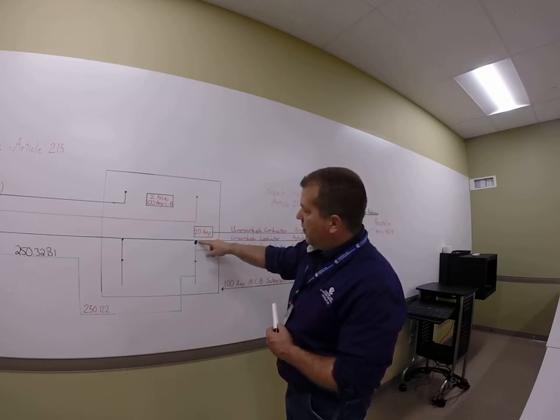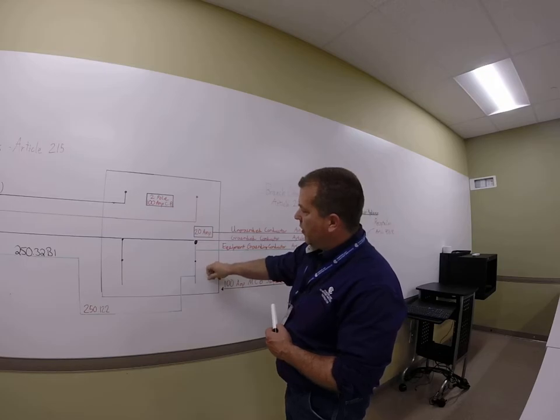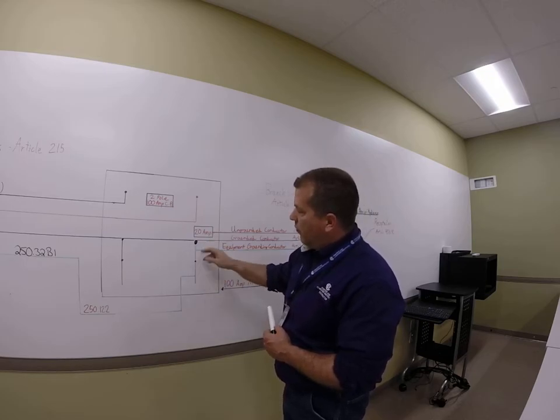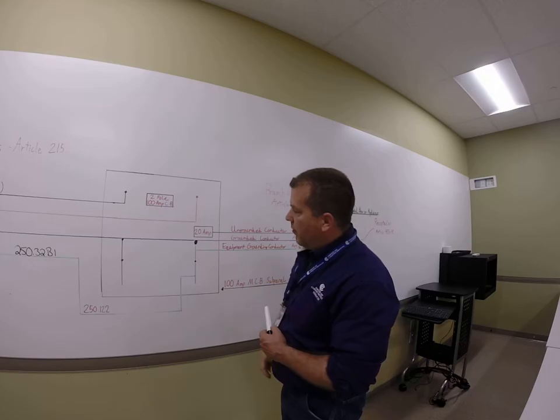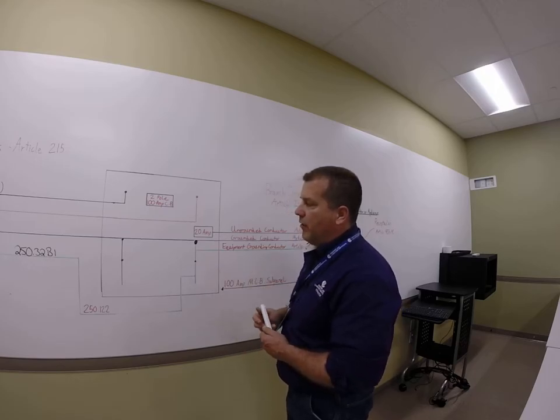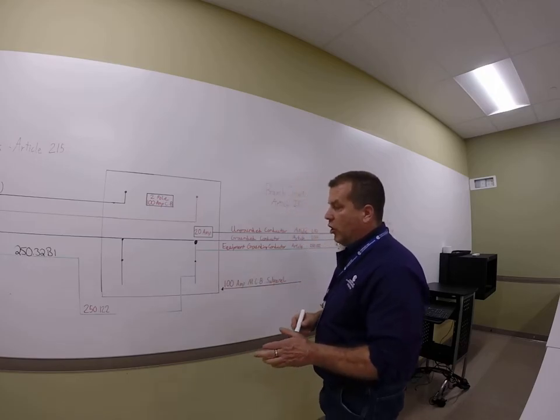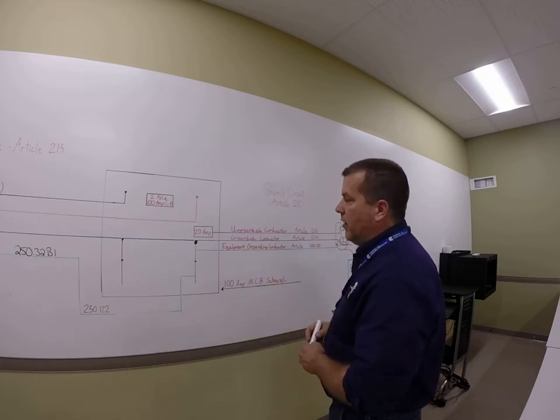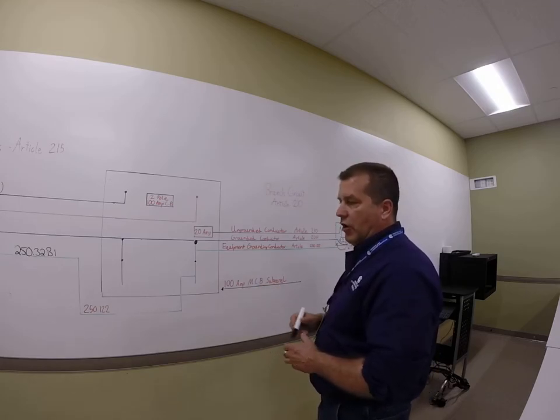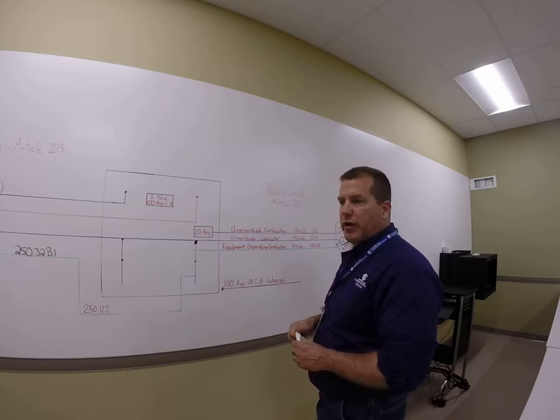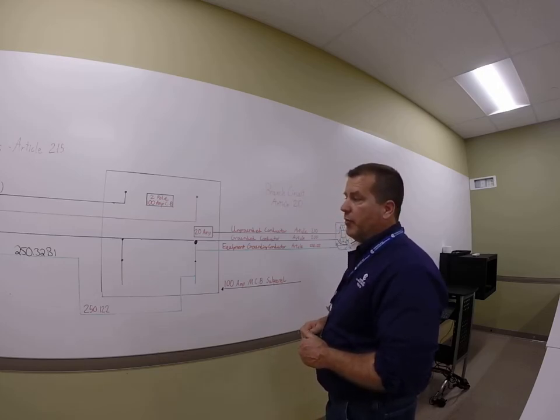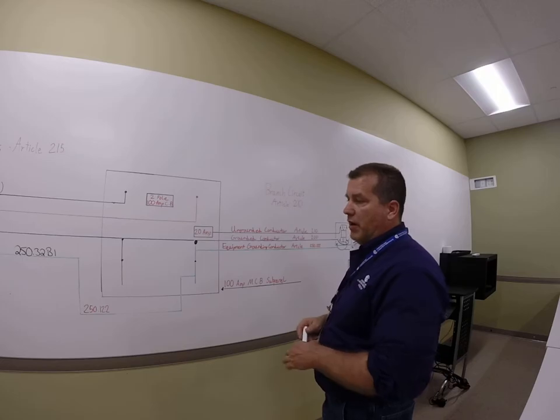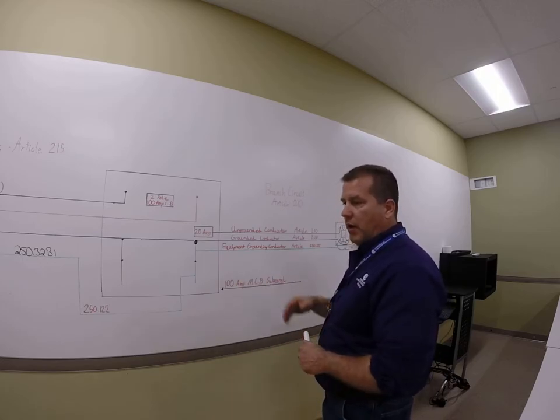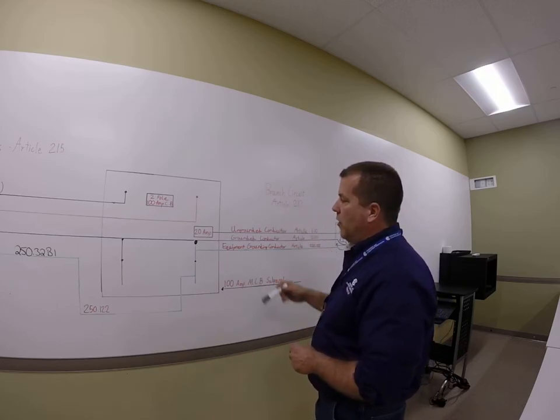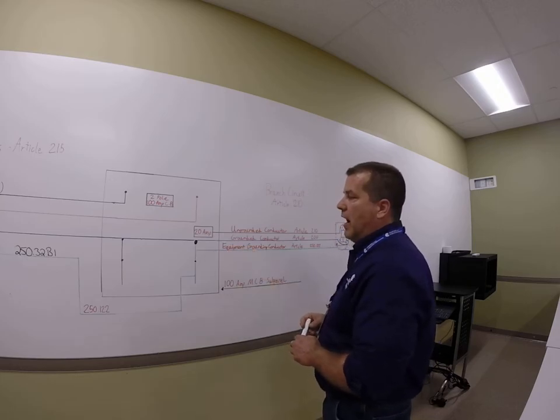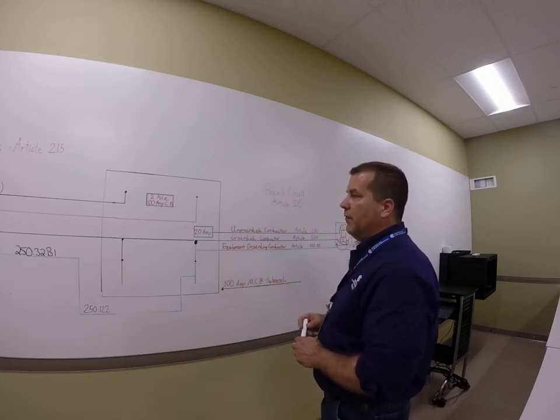They're like, hey, let me see what's going on down here. This is low impedance. And all of a sudden you get a residual, objectionable amount of current on that equipment grounding conductor. So not a good thing, because most of the time that equipment grounding conductor is bonded to other metal objects that could be in that building. Very often in a commercial building, a lot of our metal is bonded to framing steel and building steel. And you don't want objectionable current on that system coming from a sub panel.